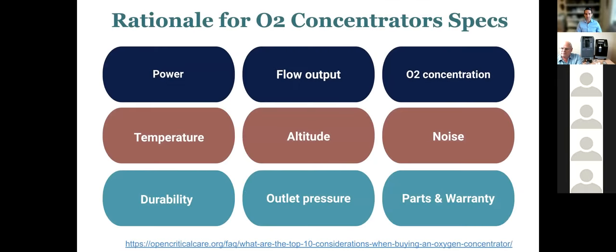I'll talk a little bit about the rationale for some of the specifications around concentrators. Most of this is a summary of what's in the WHO specs, so you can read more about it there. Just going to touch on some of these briefly. Power: we've already talked about power a little bit, making sure that it's compatible with the local power supply, but also power efficiency, ensuring that the amount of power this oxygen concentrator consumes is reasonable, not so much that it's going to cause power supply issues no matter where it is. I think the recommendation is less than about 70 watts per liter per minute, but please reference the WHO specs on that. That's an important one.